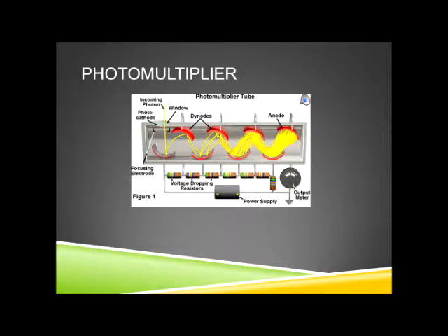Some of the most important are photomultipliers, photodiodes, and photovoltaic cells. A photomultiplier consists of a source of primary photoelectrons, a photocathode, and consecutive secondary electron emitters known as dynodes. Each subsequent emitter is supplied with high electrical potential in comparison with the preceding one. Photoelectrons produced by the photocathode are accelerated to the first emitter, ejecting secondary electrons from its surface. The latter are then accelerated to the next emitter, knocking out even more electrons.